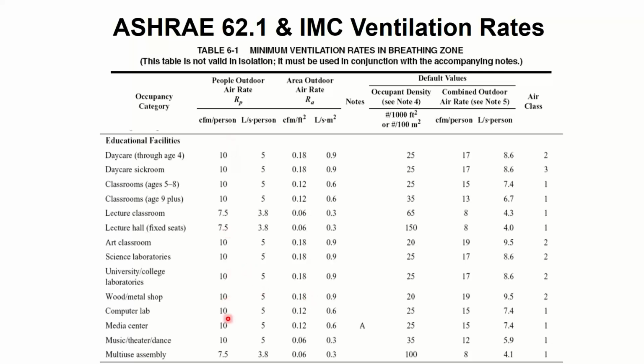By the way, all of these numbers are pretty large. They're larger than most other spaces. So for example, a typical office building is 5 CFM per person instead of 10 and 0.06 CFM per square foot instead of 0.12. It's literally half the ventilation rate of a classroom. So the codes are pretty strict on schools, making you guys bring in a lot more fresh air than other types of spaces might require.